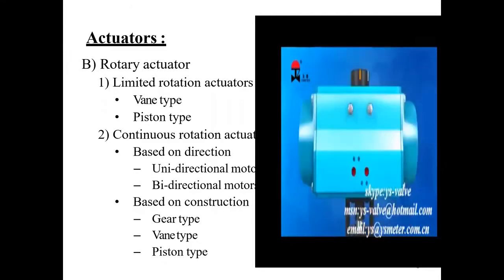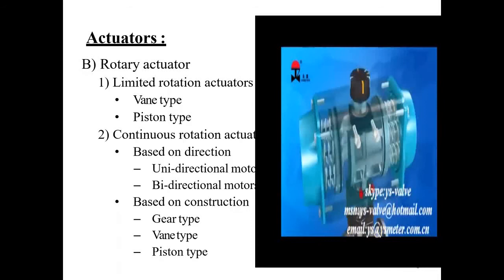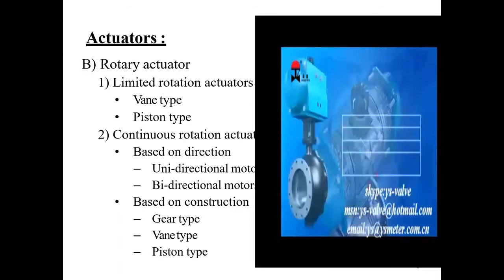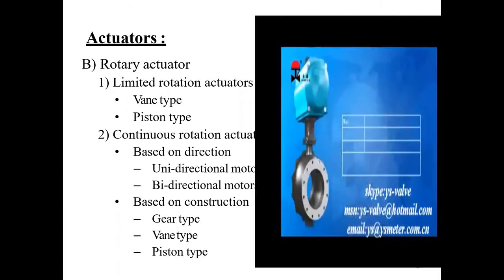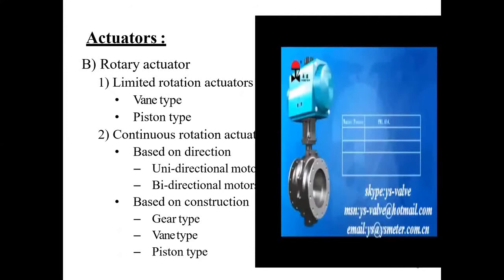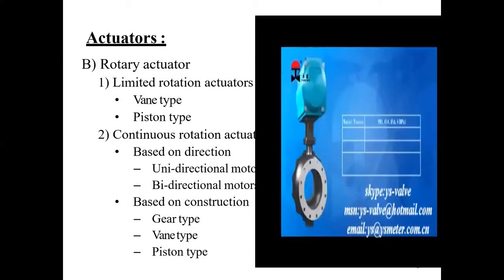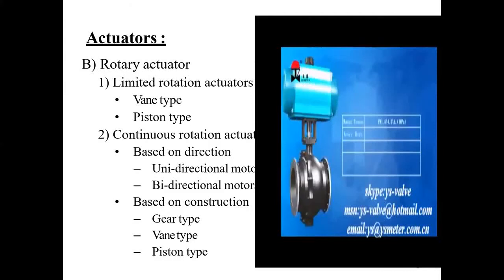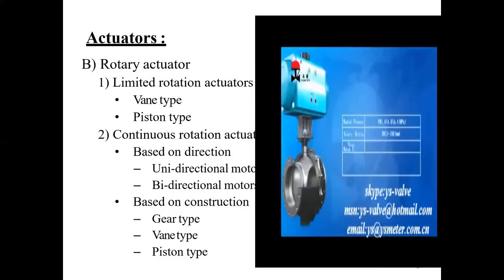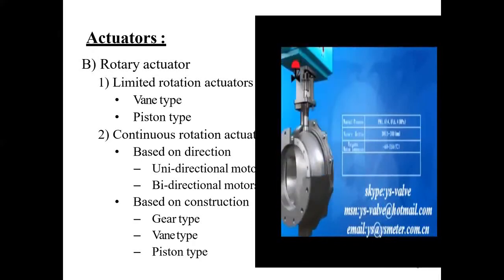The actuator chooses high-performance dual-piston pinion and rack mechanism, ensuring high driving efficiency and compact design. The nominal pressure rating of this series is PN 1.6, 4.0, 6.4 MPa. The valve's orifice range is DN 15 to 300 millimeters, and the applicable medium temperature is 60 centigrade below zero to 250 centigrade.